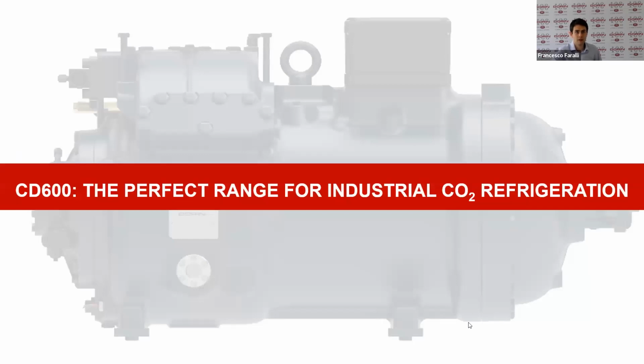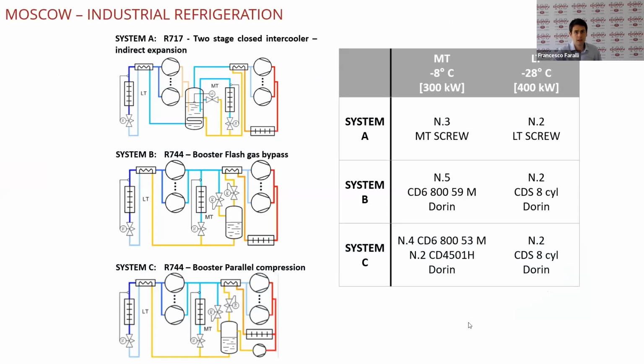And here is an example of CO2 in industrial refrigeration using the CD600. We have made a comparison between ammonia and CO2. The first system is an ammonia system using a screw compressor. The cooling capacities are 300 kilowatts at -8 and 400 kilowatts at -28. System A is with ammonia, system B and system C are with CO2. System B is a booster flash gas bypass system using 7 compressors, CD600 for the transcritical side and CDS for the subcritical side, and system C is also made of CO2, but it's a booster system with parallel compression, so a little bit more complex system, but also a little bit more efficient.